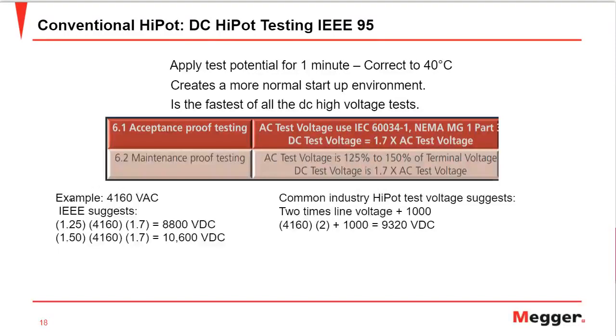And there are various standards to determine what our test voltage should be when doing a DC high-pot. As per what IEEE 95 suggests, our DC test voltage should be 1.7 times the AC test voltage, and it can be between 125% or 150% of the terminal voltage. So for a 4160 volt AC motor, our test voltage could be between 8800 volt DC or 10,600 volt DC.